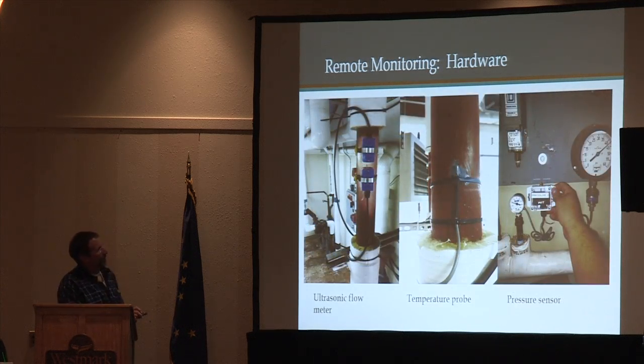Here's some of the sensors. What we were trying to do, to the degree we could, was send a technician out and install these without a lot of hard wiring, plumbing, or cutting pipes. So what you see here is 3 of what we're trying. This is an ultrasonic flow meter, a $120 unit you can only buy on eBay, but it's been working pretty good, though it's kind of a pain to set up.